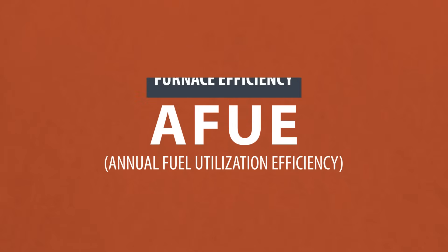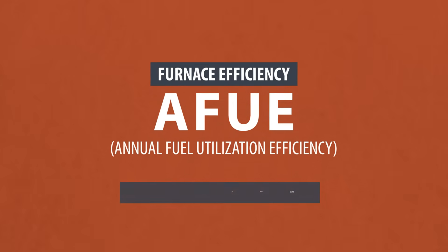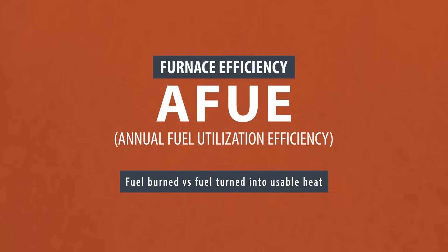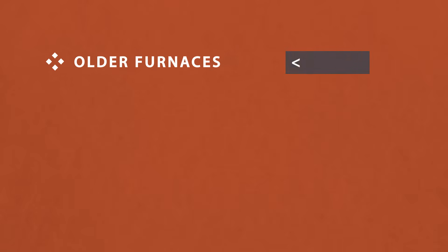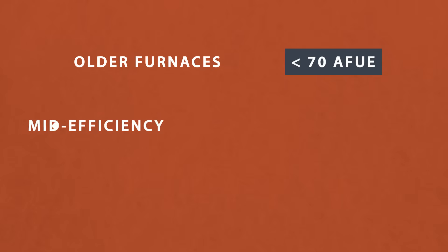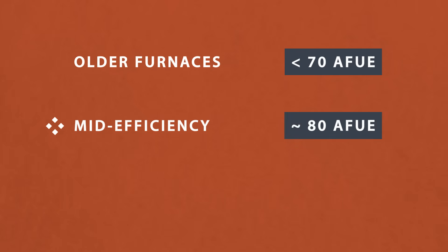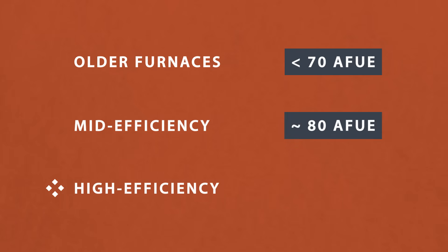Furnaces are rated by AFUE, or Annual Fuel Utilization Efficiency. This number is a ratio of the fuel burned versus the fuel converted into heat. Older furnaces will have an efficiency rating of 70 AFUE or less, meaning that only 70% of the fuel is turned into usable heat. Mid efficiency furnaces are around 80, and high efficiency condenser furnaces are generally 90 and above.